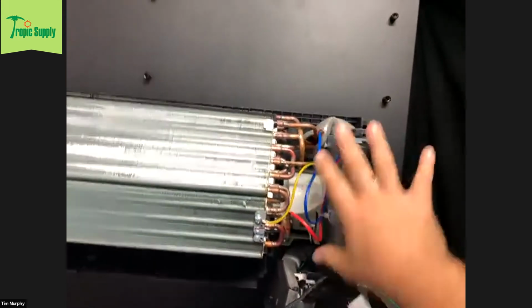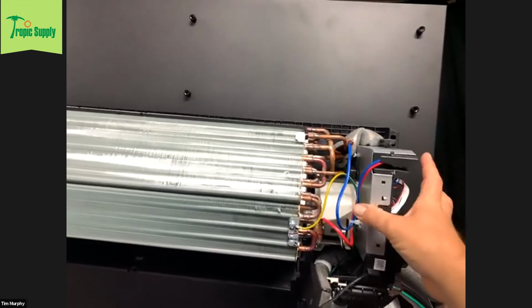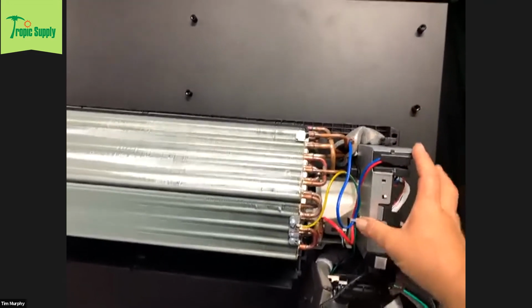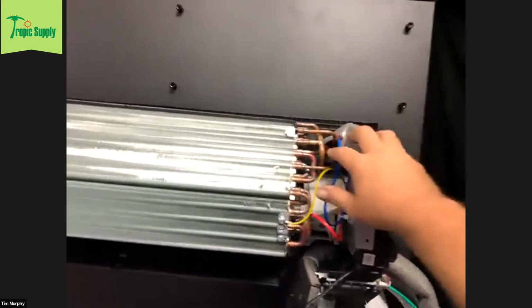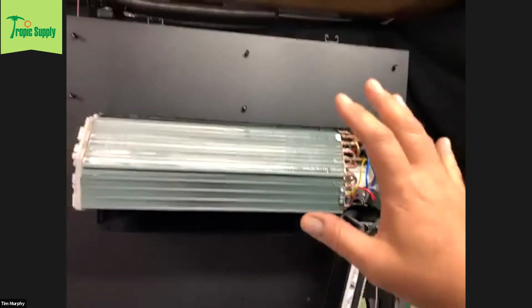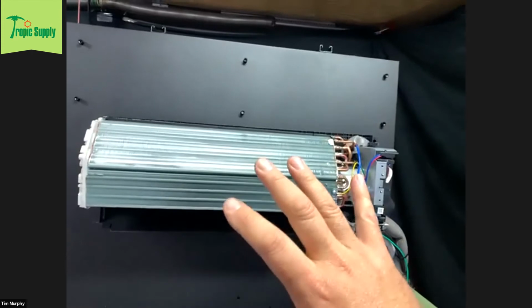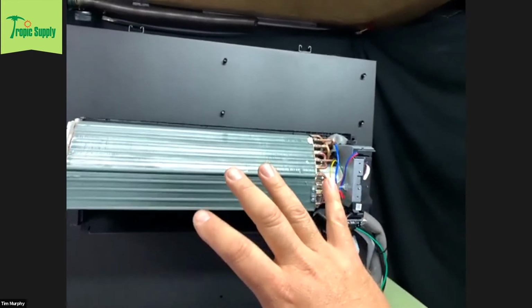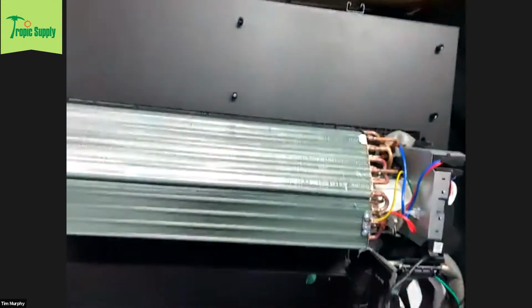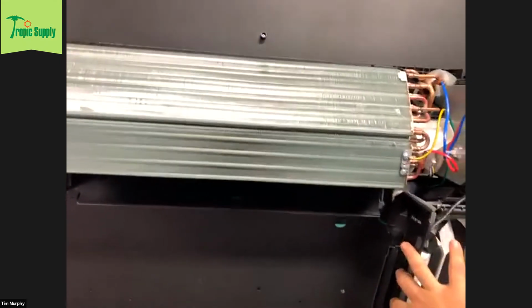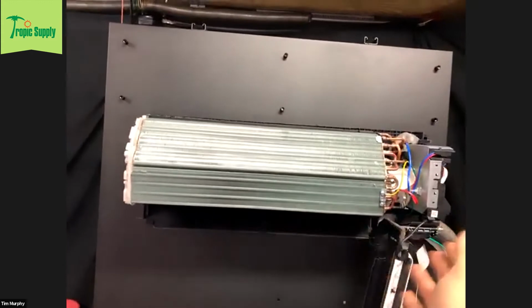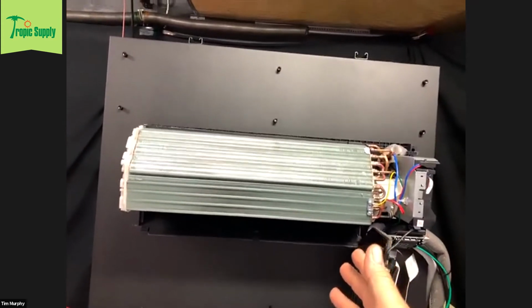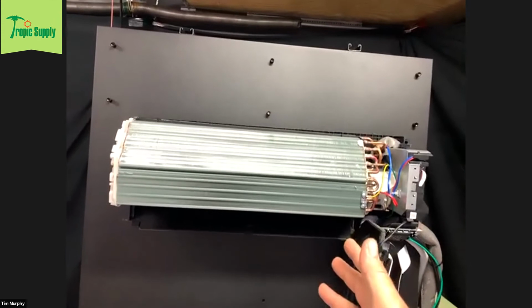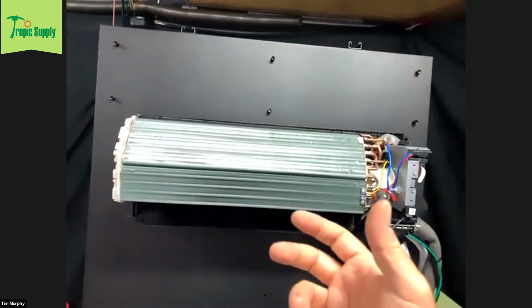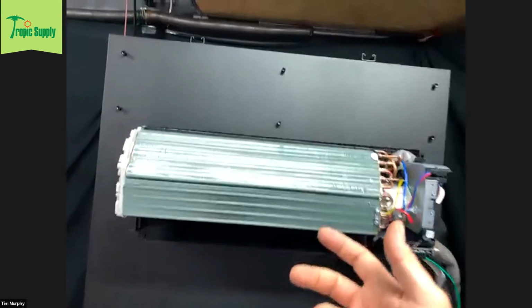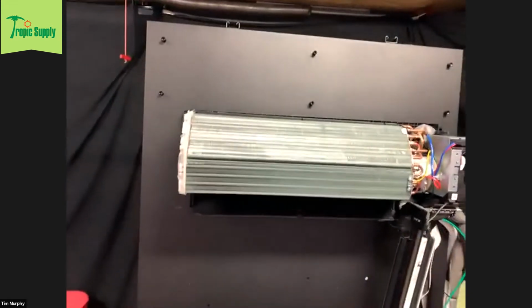Put a little plastic cover over this. What's good on the Samsungs is they're pretty well covered, so I'm not too worried as long as you don't spray it directly. But if your experience is minimal with this style of system, I recommend putting the bib kit on, dropping the drain pan, and then using a powered sprayer or whatever method you're going to use. Typically you want some kind of powered water in there, whether it's a hose or something like that. Obviously you don't want to drench it because you'll fill up the bucket super fast.